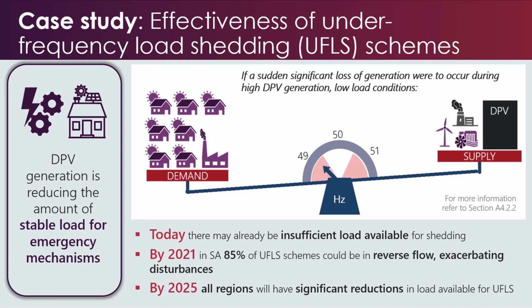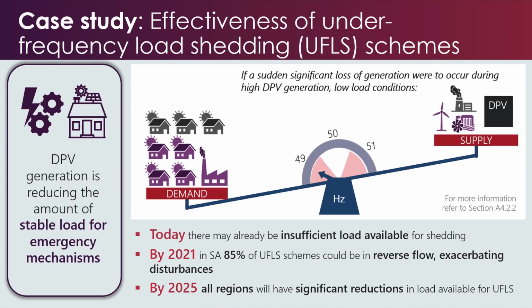Where the frequency drops significantly, the UFLS scheme may autonomously activate frequency-sensitive relays in order to rapidly rebalance the supply and demand. However, if a lot of the load has distributed PV associated with it, these feeders could be operating as net generators or in reverse flows. This means that in net terms, the houses in a street are generating more from solar than they are consuming. So we have not only turned off some demand from the houses, but we've actually turned off more supply coming from the DPV as well. Instead of solving the issue, this actually exacerbates the supply-demand imbalance.